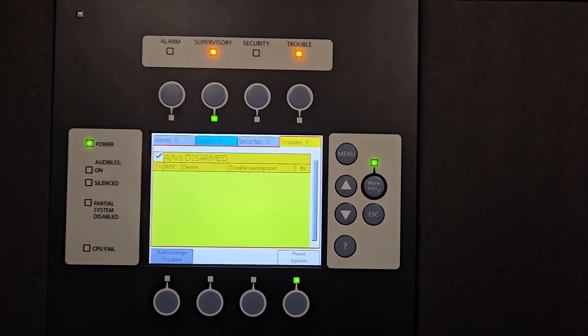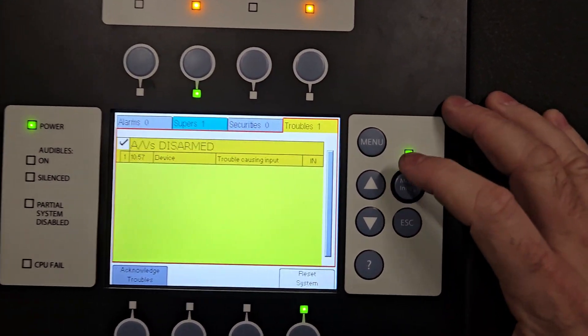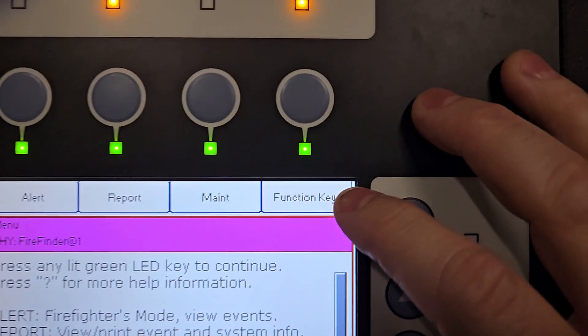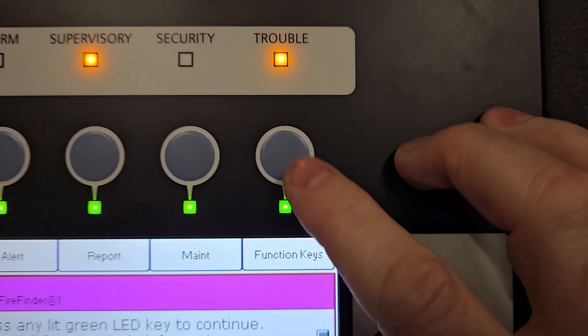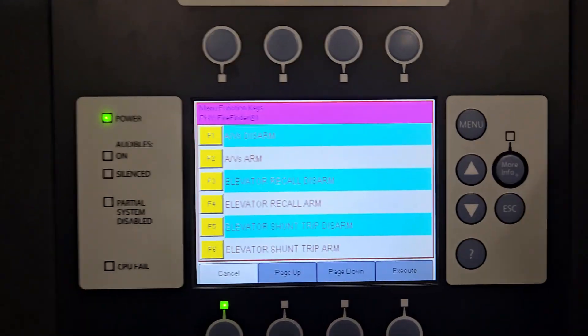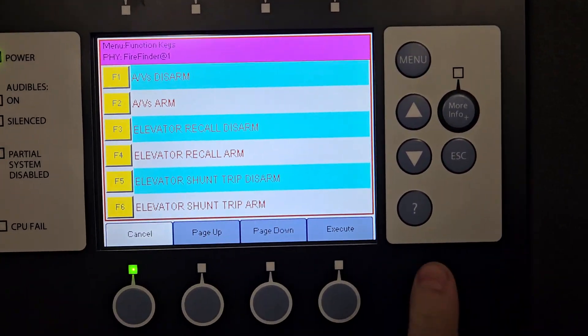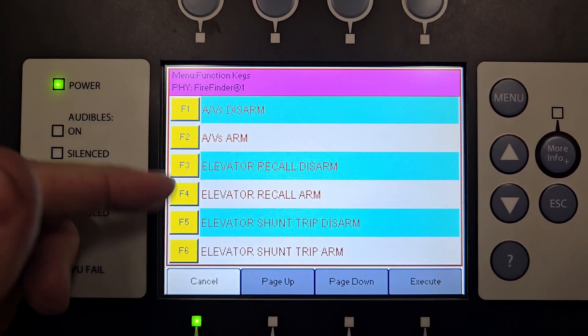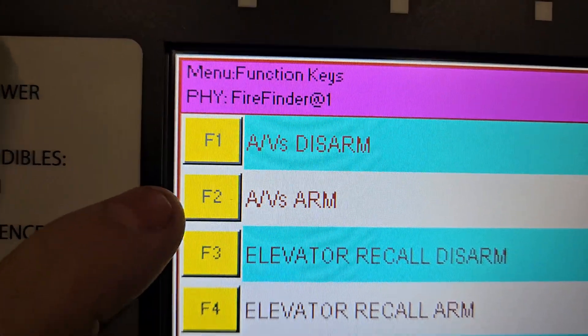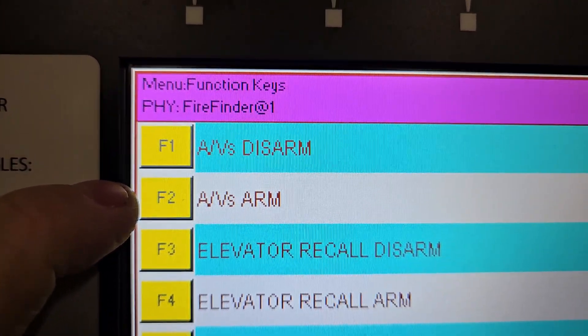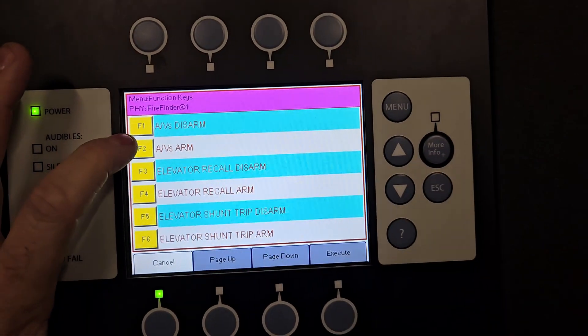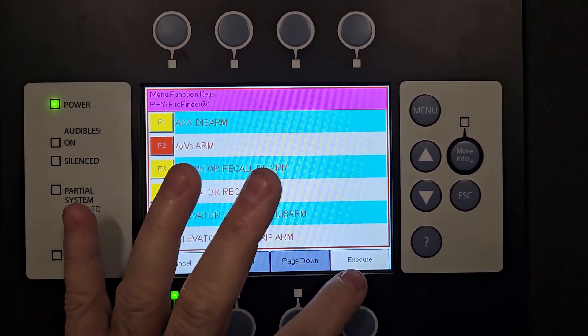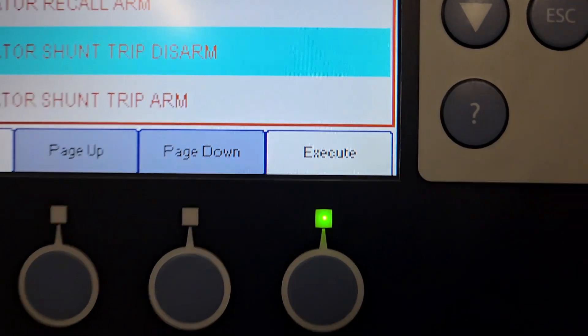At the end of the day, I want to put the system back to normal. So I'll do a reset to clear any alarms, then go into the menu button again and go to my function keys on the right. I'll hit the right button — function keys — and then I have my options again. Nothing's lit up for execute and none of my F buttons are lit. So I'm going to go to F2 to arm the audio-visual circuit. I hit that, it turns red, and the execute button lights up. So now I'm going to hit execute.